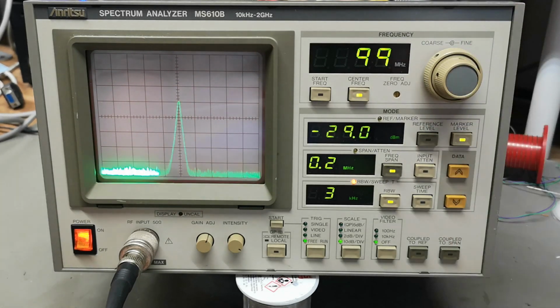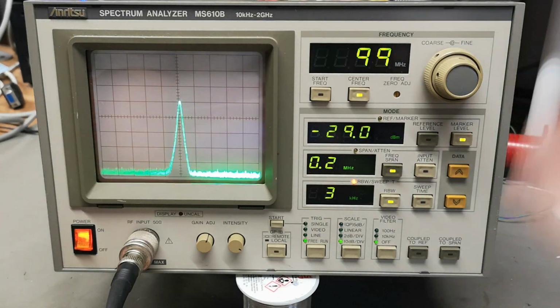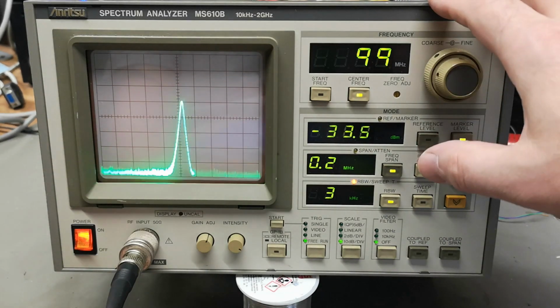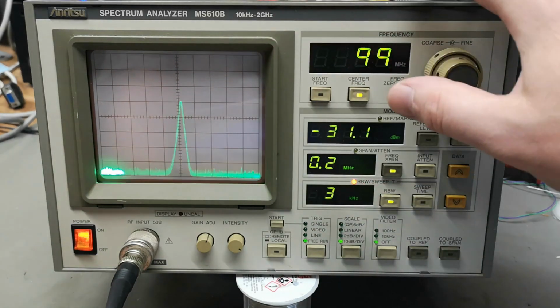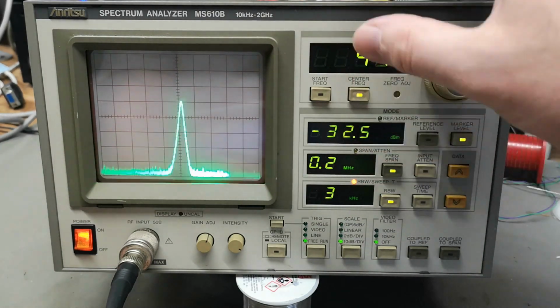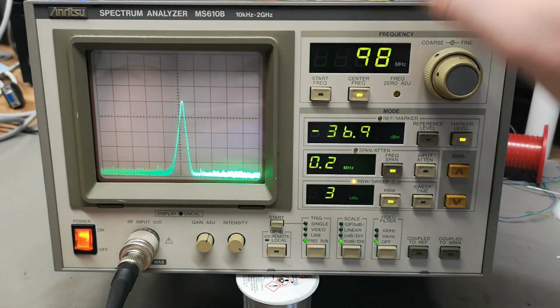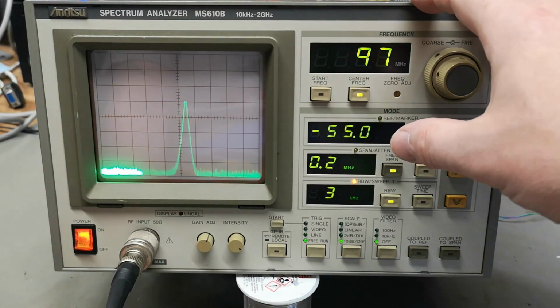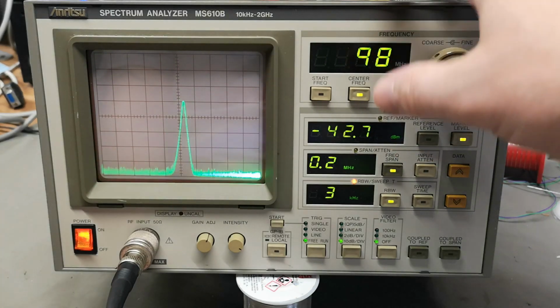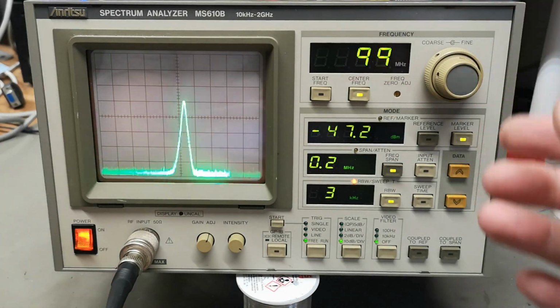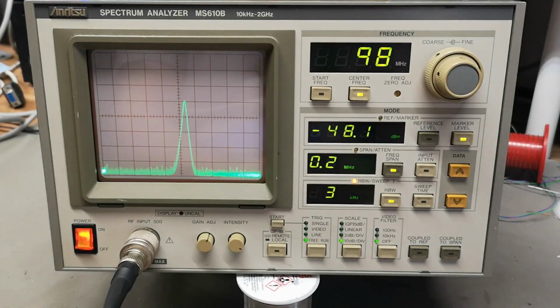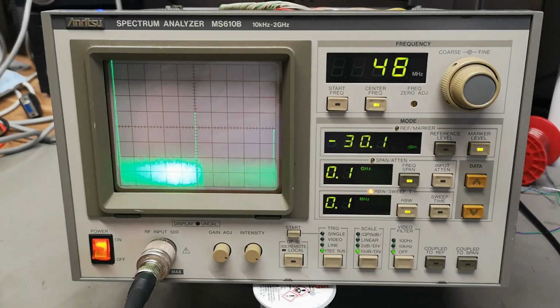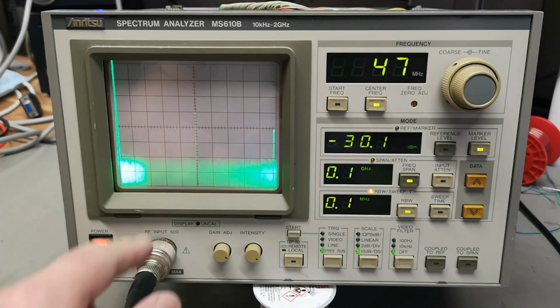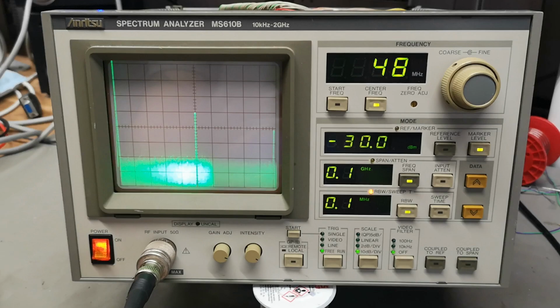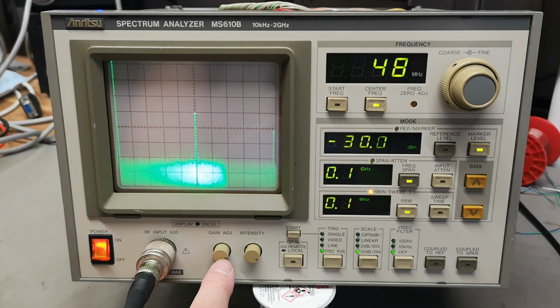Maybe we should test its calibration output and see if that is accurate. By the way, the calibration oscillator in this unit is just a free running oscillator. It's not locked to anything at all. It's just controlled by a positive 12 volt supply. And so of course, if that 12 volt supply is accurate, then I should have my output. I'll try and play with that. So here we're actually using the spectrum analyzer to measure its own 50 megahertz calibration output. And of course I had to dial this up a little bit because it is a little on the low side.